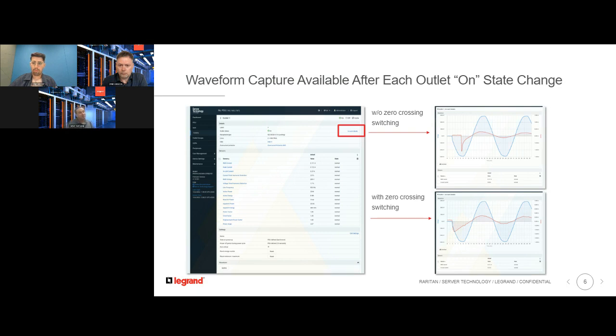Those switch PDUs are used a lot of different ways for remote reboot, and often switch PDUs are also used to turn off the unused outlets. So as people are doing work in the cabinet, they don't plug in things they shouldn't, or move things around, or cause other problems with the branch loading or the three-phase load balancing. So it's kind of a culmination of all those advanced features, technology that we've been doing for years that we're refining or tuning, and then all the power quality, all the waveform captures, and all these use cases that our customers have told us are problems within their data center, rolled up uniquely into our new PDU solutions.